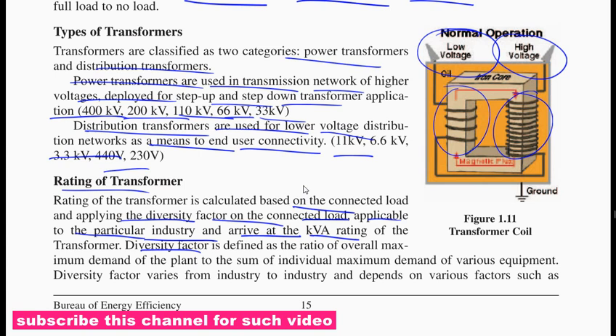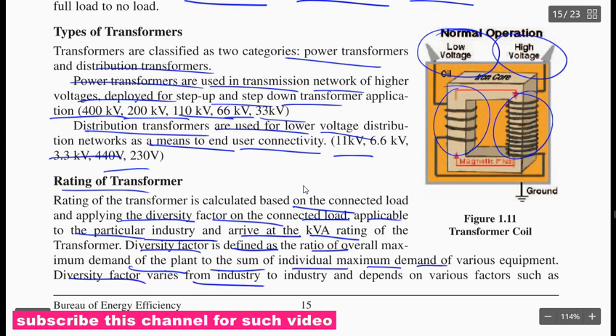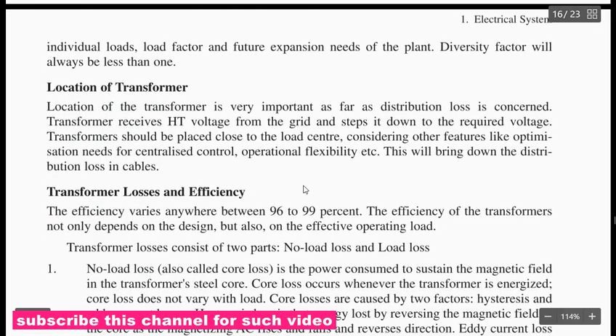Next, transformer. Diversity factor is defined as the ratio of overall maximum demand of the plant to the sum of individual demand of the various equipment. Diversity factor varies from industry to industry and depends on various factors such as individual load, load factor, and future expansion needs of the plant. Diversity factor will always be less than 1.